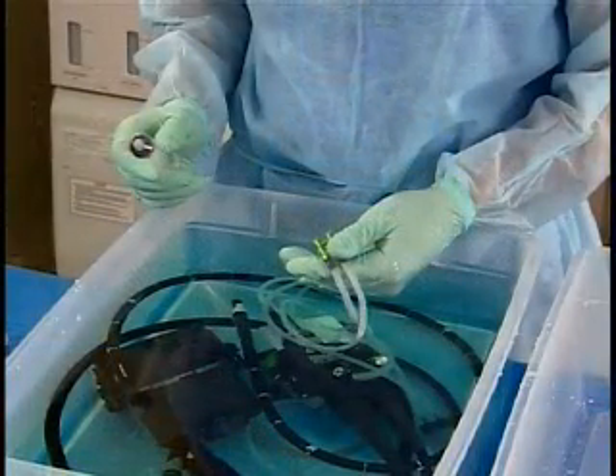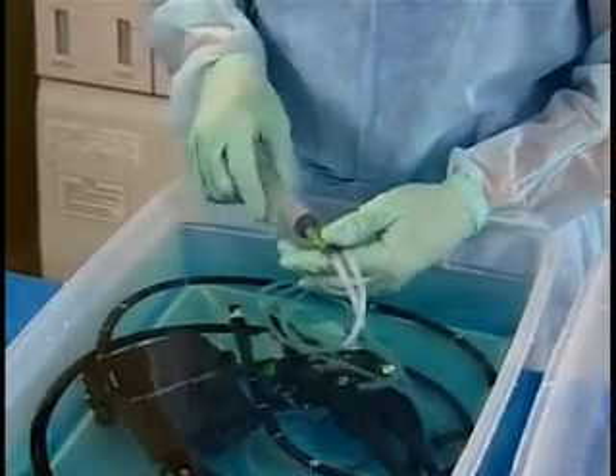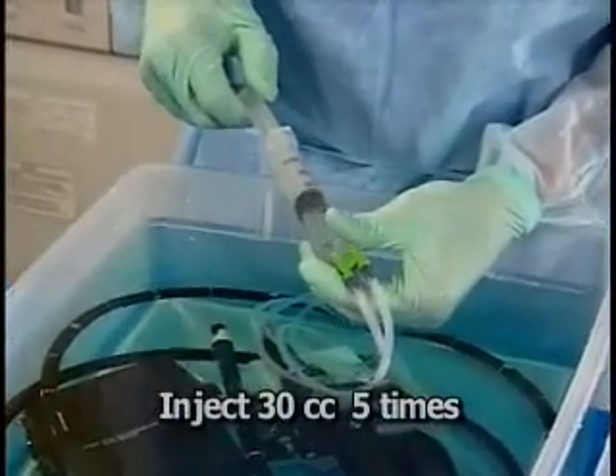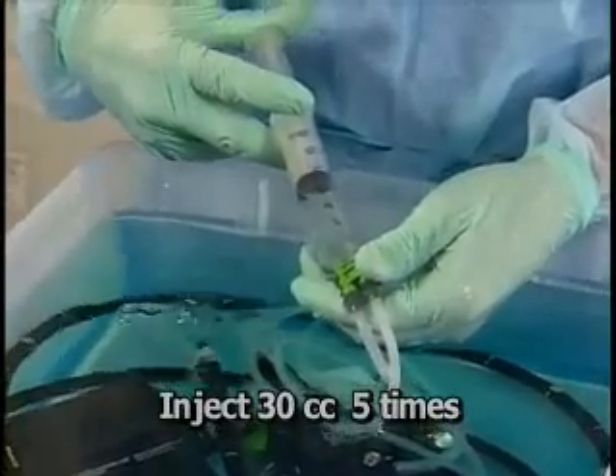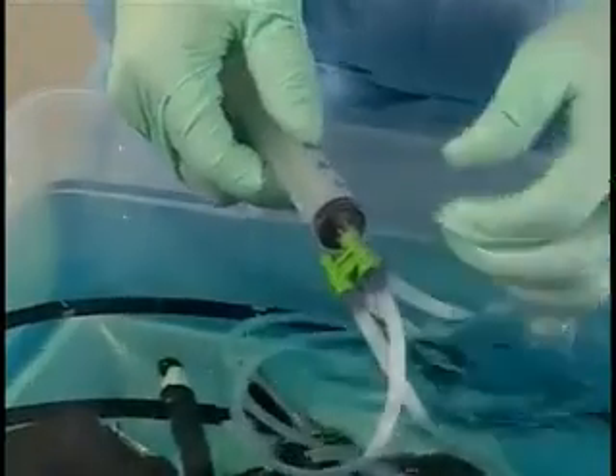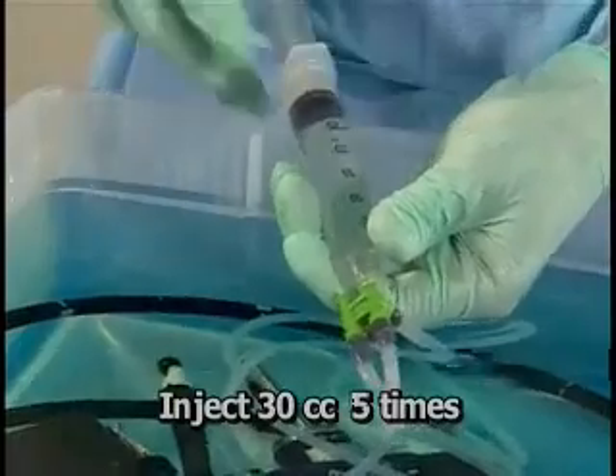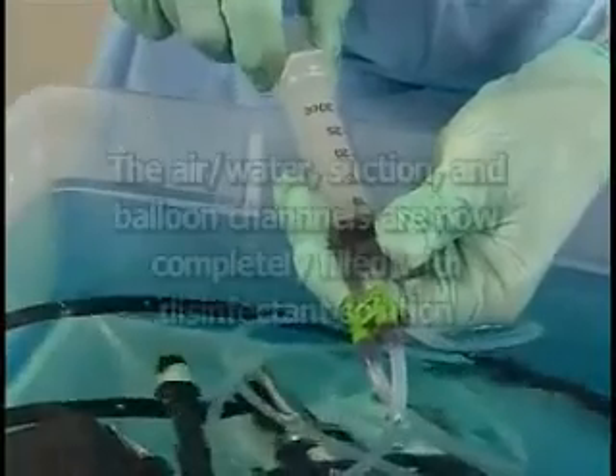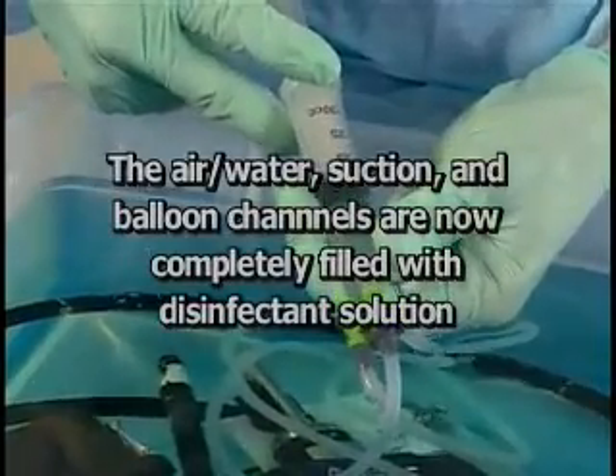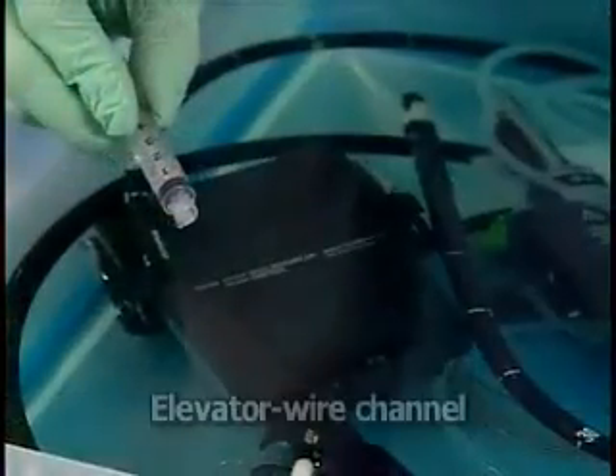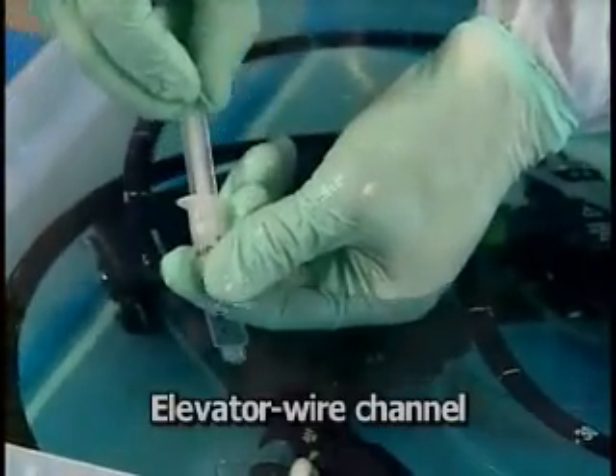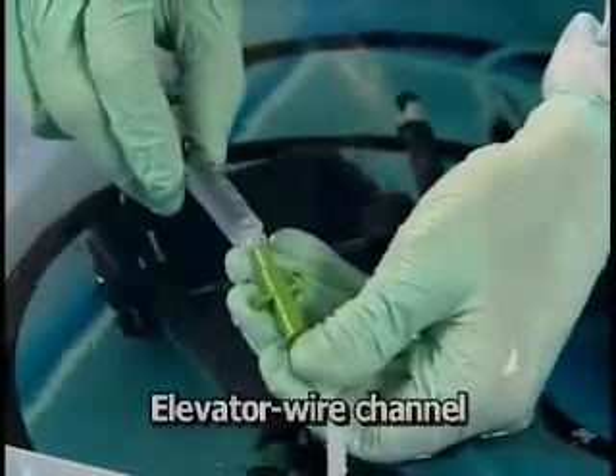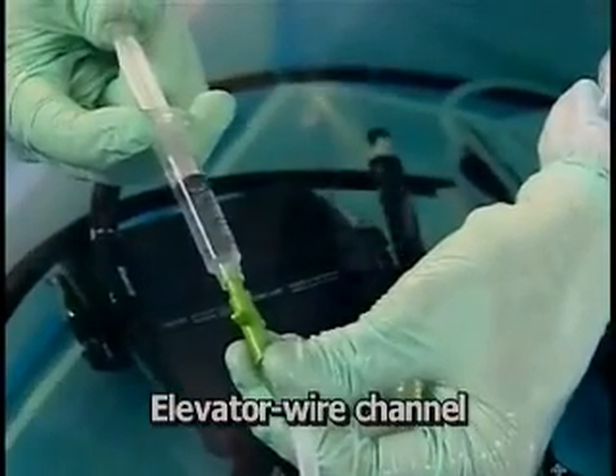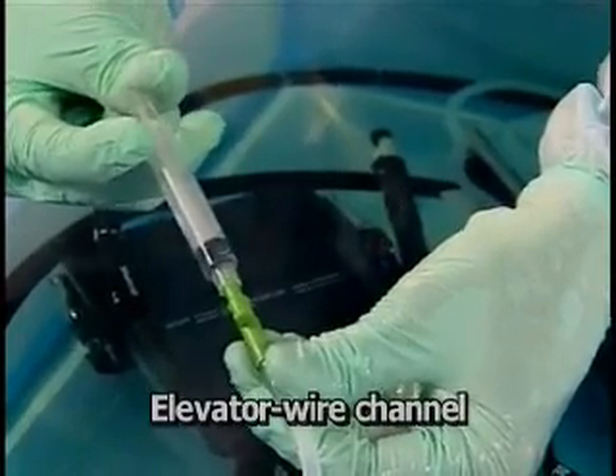With the cleaning accessories attached and the intake filter immersed in disinfectant solution, use a 30 cc syringe to inject 150 cc's of disinfectant into the air, water, and balloon channels. Repeat this procedure with the syringe attached to the suction channel port. The endoscope's air-water suction and balloon channels are now completely filled with disinfectant solution. If you are reprocessing an endoscope with an elevator, inject disinfectant into the elevator wire channel using a 5 cc syringe. Now, disconnect all accessories while making sure all items remain submerged.